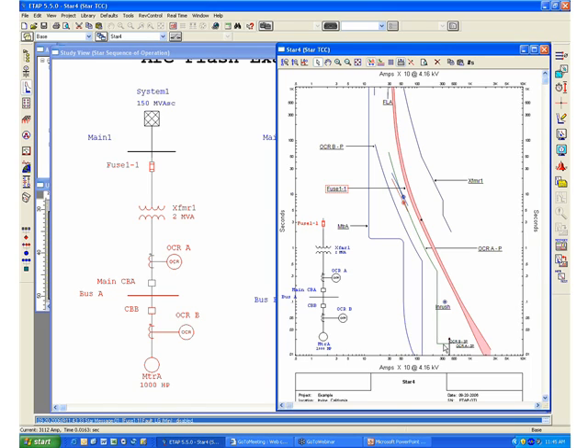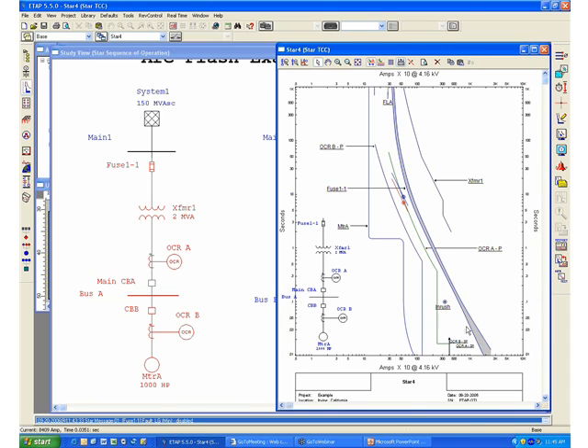This eliminates some of the work of having to generate all the TCCs for each part of the system. Of course, in order to validate your results, you may want to generate a time current characteristic curve to check the result and see if there is any way of limiting or reducing the amount of incident energy that could be released in the event of an arc fault.